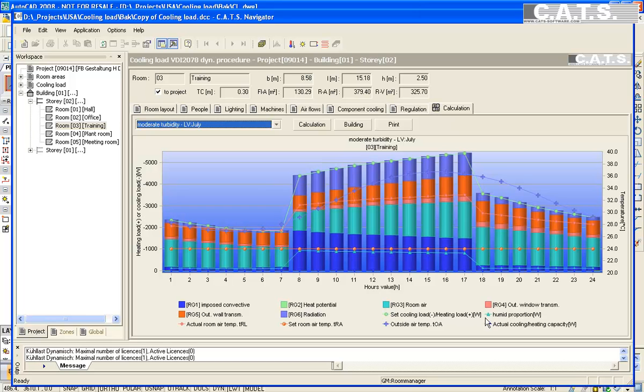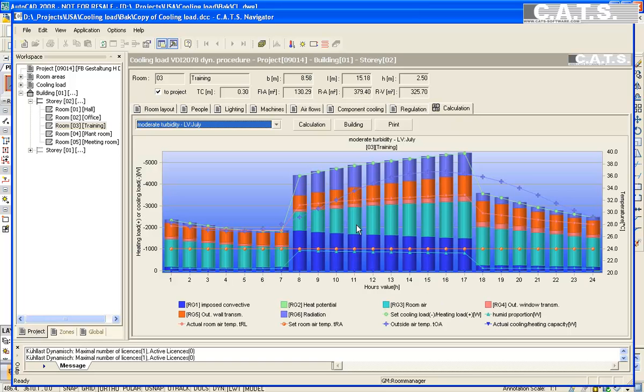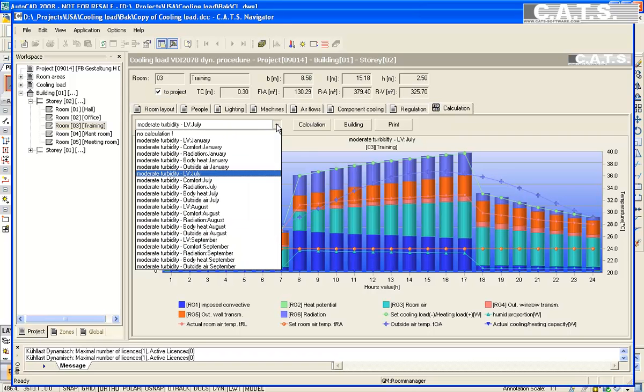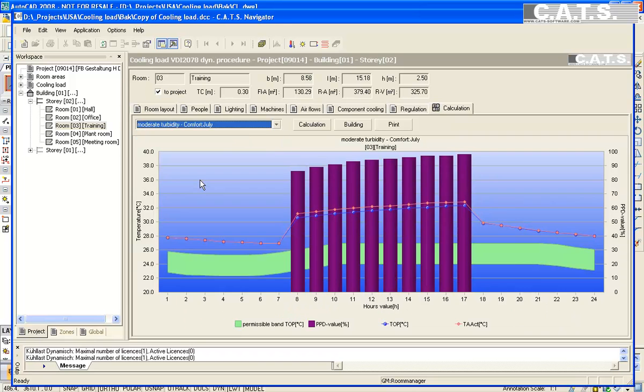We will select the system actual capacity, which is zero as the system is turned off. We look at the comfort level of the room. The light green band indicates the comfort zone. The purple columns indicate the predicted percentage of dissatisfied people due to the room conditions. The red line indicates the actual room air temperature. The blue line indicates the actual operative temperature.